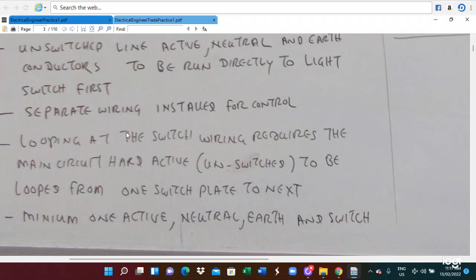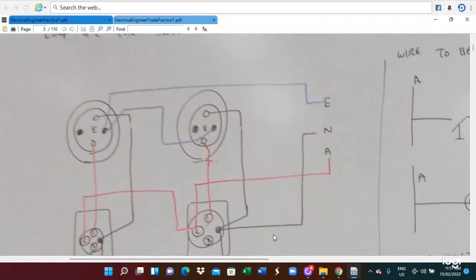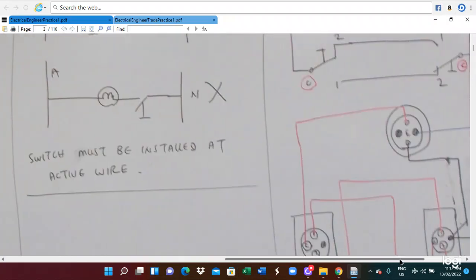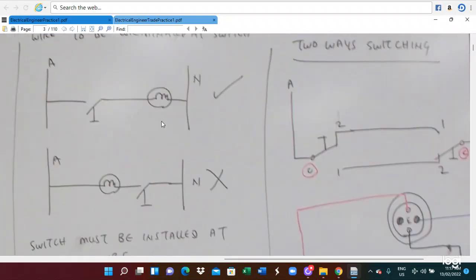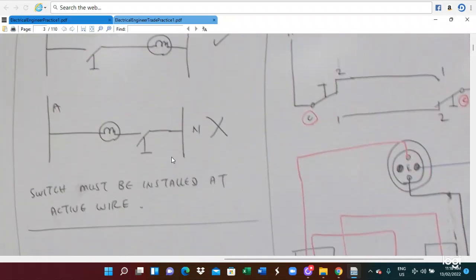Then looking at the loop-at-the-switch wiring, they require the main circuit active to be looped from one switch plate to the next, with a minimum of one active, neutral and earth at the switch. So when you connect, the important thing is the switch must come in first: active to switch, and then light to neutral. If you put the light before the switch, it's wrong, because the switch must be installed on the active wire.